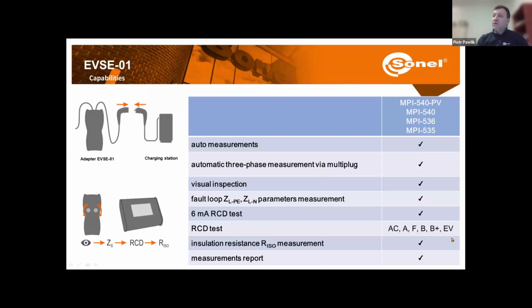I know that the older models, like for example the MPI 520 that we developed maybe 15 years ago, cannot check the DC leakage current of 6 milliamps. So that would be a limitation for some older designs of meters, but the newer designs can perform all of the tests and give you the summary from which you can create the report.